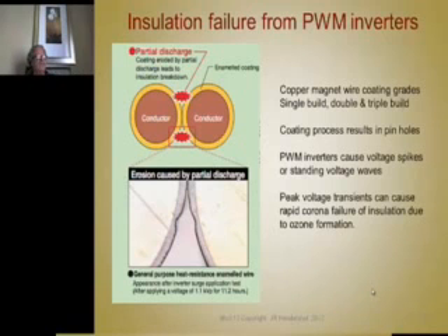you control the current with PWM. Remember, the currents are controlled all the way down those leads, so you turn the voltage on and off at some PWM frequency. What this results in is standing voltage waves, very high voltage waves, that oscillate at PWM frequency in these lead wires, these long cables that go to the phase windings. So these are big, huge voltage waves, 3,000 volts maybe, 4,000 volts. So on adjacent conductors, if there are any fine little weak spots in the insulation of this conductor and it's close to that one, particularly on the first turn of the first coil of each phase, the coils that are out at the end of the Y connection or close to the delta connection.